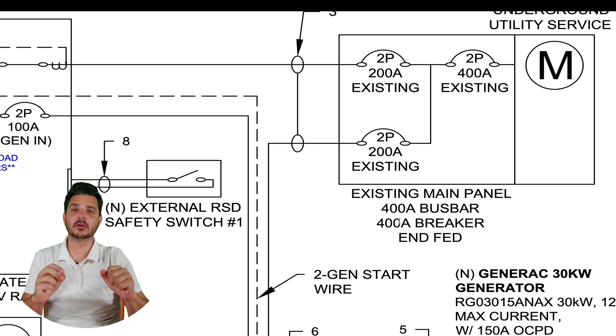You rarely get actually a 400 amp bus bar on most 400 amp residential homes. Typically it's a 200 amp bus bar with a 200 amp breaker passing through to a sub panel downstream somewhere, and then there's a 200 amp feeding that bus bar right there. So that's sure a 400 amp panel, but it's really just 200 amp sub panels, more or less.